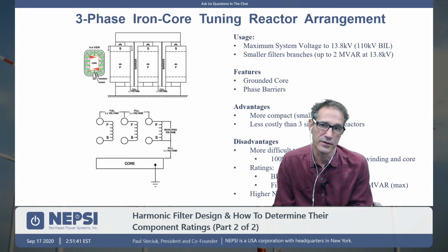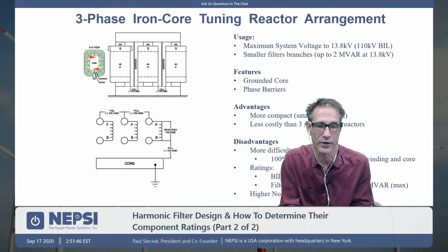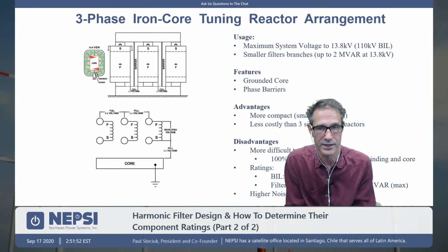The other thing is the core is grounded. If it's a 3-phase reactor, the core has to be grounded, which means that we have full voltage between the winding and the core.